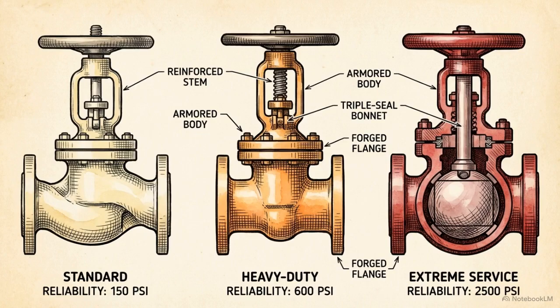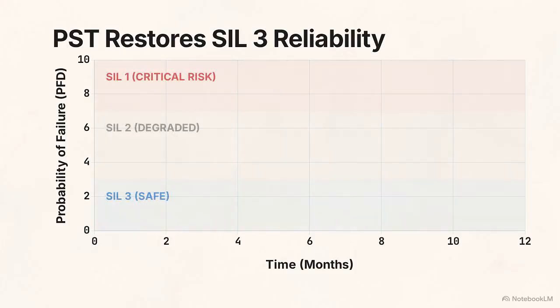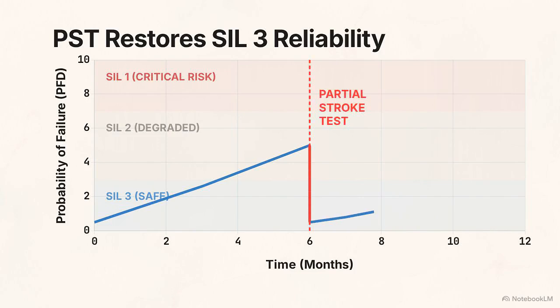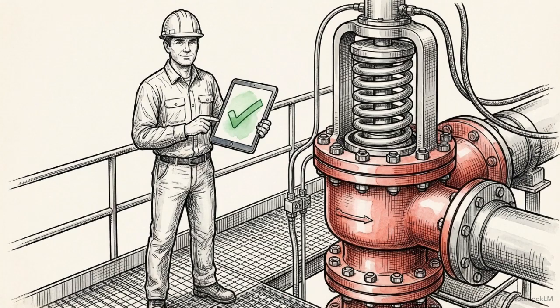Every safety function in a plant is assigned a safety integrity level, SIL 1, 2, or 3, representing its statistical reliability to perform when demanded. Routine partial stroke testing lowers the valve's mathematical probability of failure on demand, ensuring it meets its strict SIL rating. A mechanical failsafe degrades over time. It only provides protection if its physical viability is repeatedly proven through strict testing cycles.